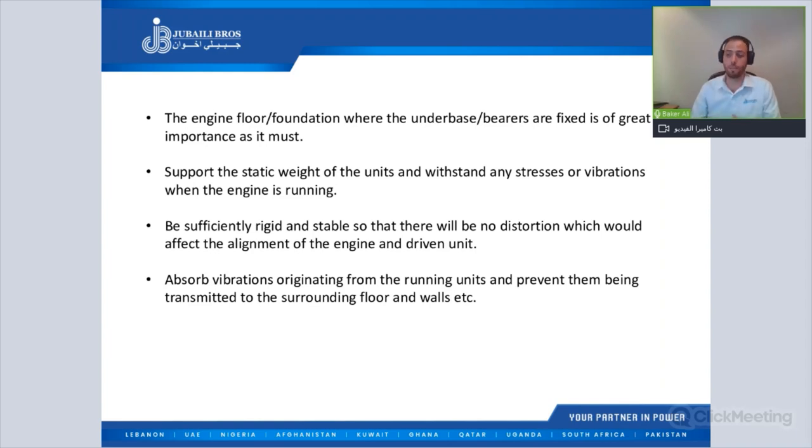So what is the importance of the generator foundation? The importance of the generator foundation is to support the static weight of the unit, withstand any stresses or vibration when the engine is running, and be sufficiently rigid and stable so that there will be no distortion which would affect the alignment of the engine and the driven unit. The third is to absorb vibration coming from the running units and prevent transmitting this vibration to the floor and walls.